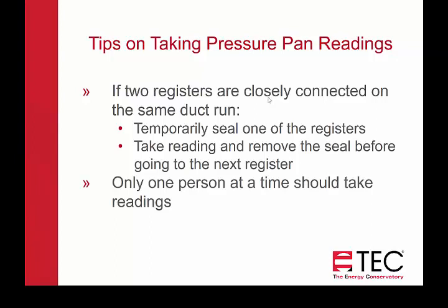Only one person at a time should be taking readings, because your readings will be affected if you have two people doing it. The building science behind it is that your readings are reflecting the ratio of how leaky the duct is to the inside versus how leaky it is to the outside. If you have two registers covered at the same time, you're decreasing the leakiness to the inside and it'll affect your readings.